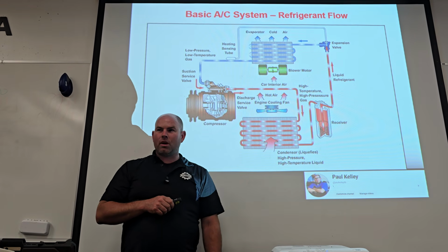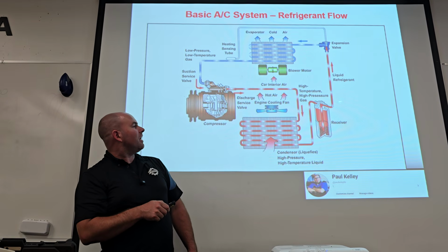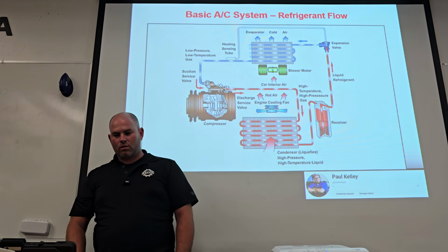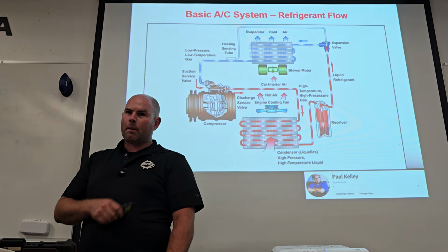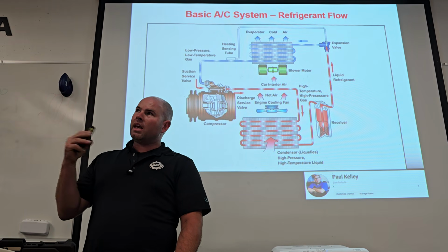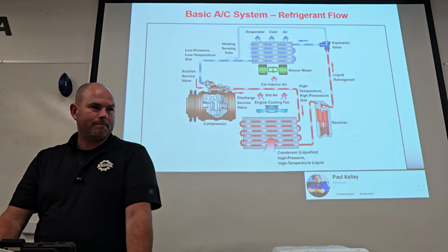Now, if the sock ruptures, next thing you got Dippin' Dots all through the system, like Mikey was saying, that can tend to clog up the restriction. That would mean your desiccant's ruptured, it needs a receiver dryer, and it probably needs a full flush, and it might have messed some stuff up too. So that's a really bad thing to have happen.